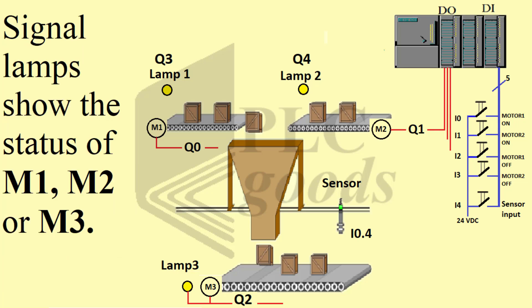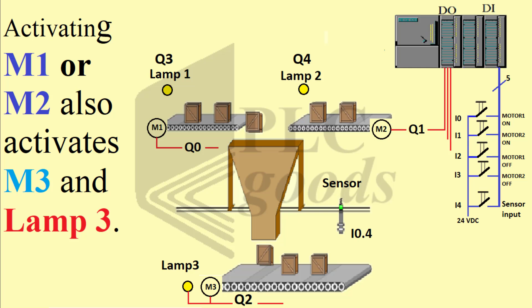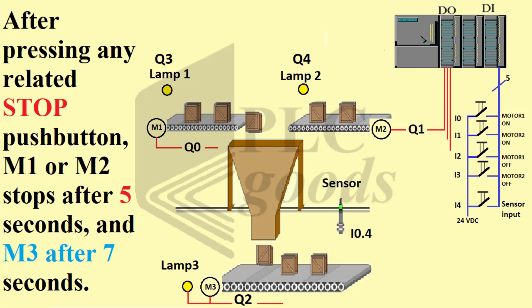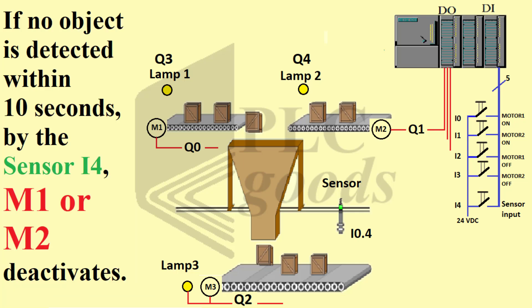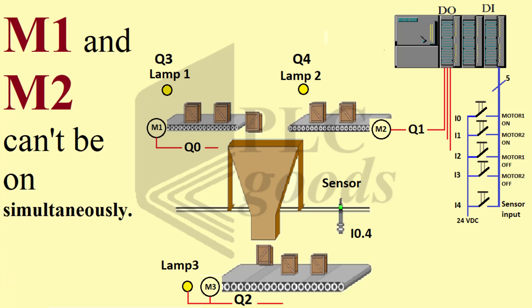Signal lamps show the status of M1, M2, or M3. Activating M1 or M2 also activates M3 and lamp 3. After pressing any related stop push button, M1 or M2 stops after five seconds and M3 after seven seconds. If no object is detected within 10 seconds by sensor I4, M1 or M2 deactivates. M1 and M2 cannot be on simultaneously.